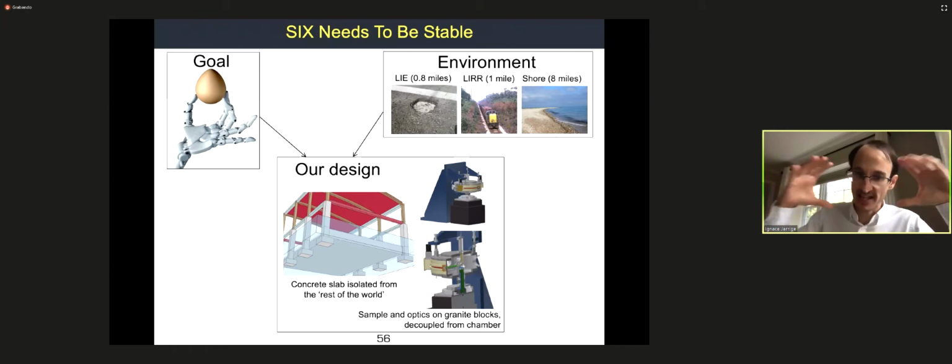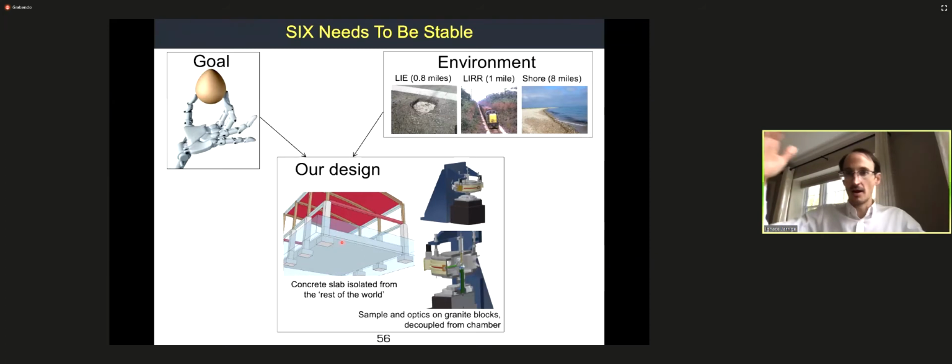We have a very thick slab of concrete built on that engineered sand, which is basically decoupled from all the foundations. Okay, so we have a rubberish layer all around it that avoids any rigid coupling between the slab and the foundation of the building. So if the wind is hitting the walls of the building pretty badly, you will hear it, because it induces lots of vibration in the walls, but that will not propagate back to the floor.